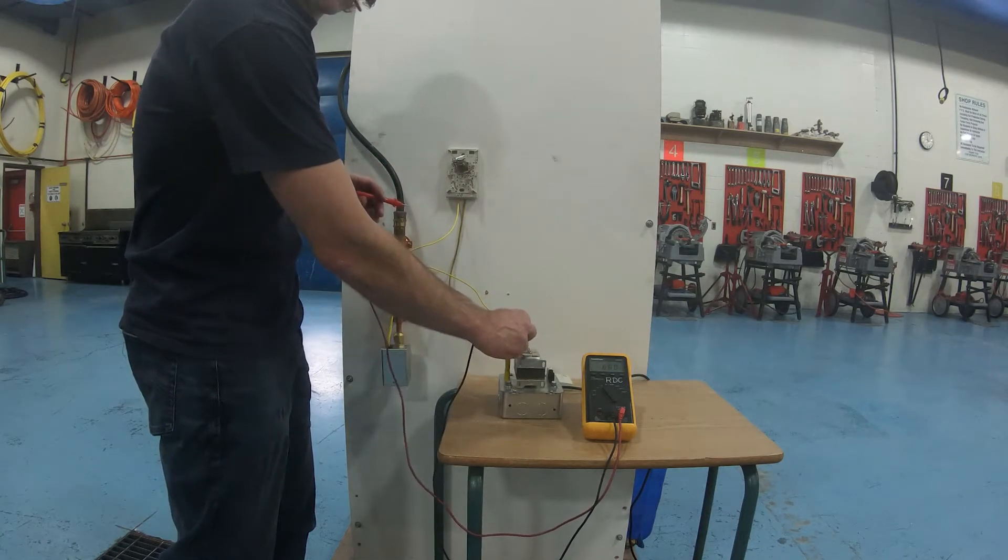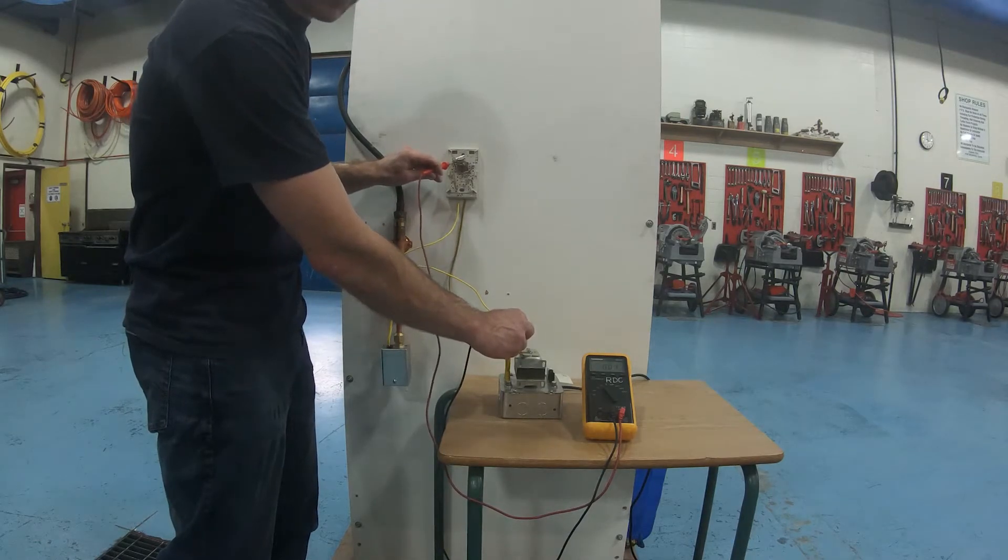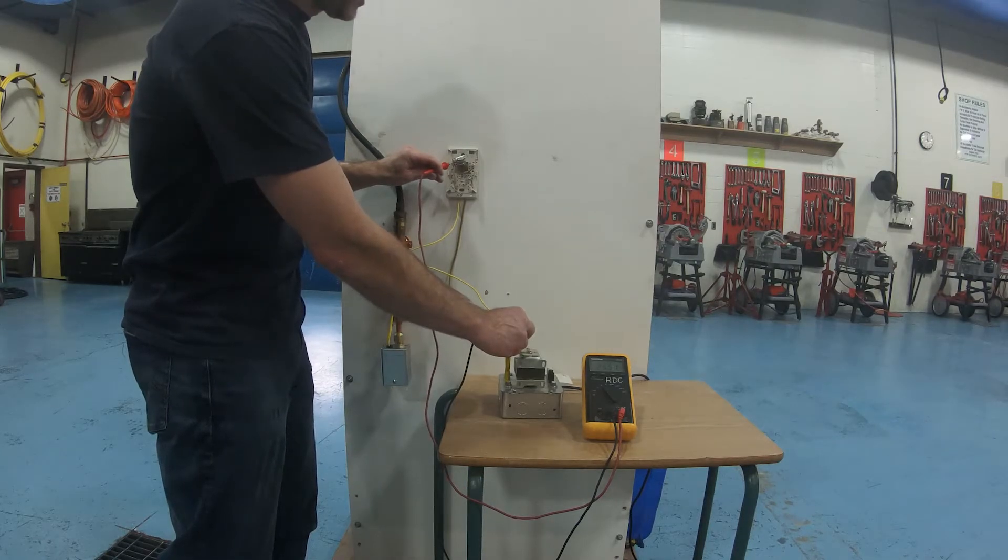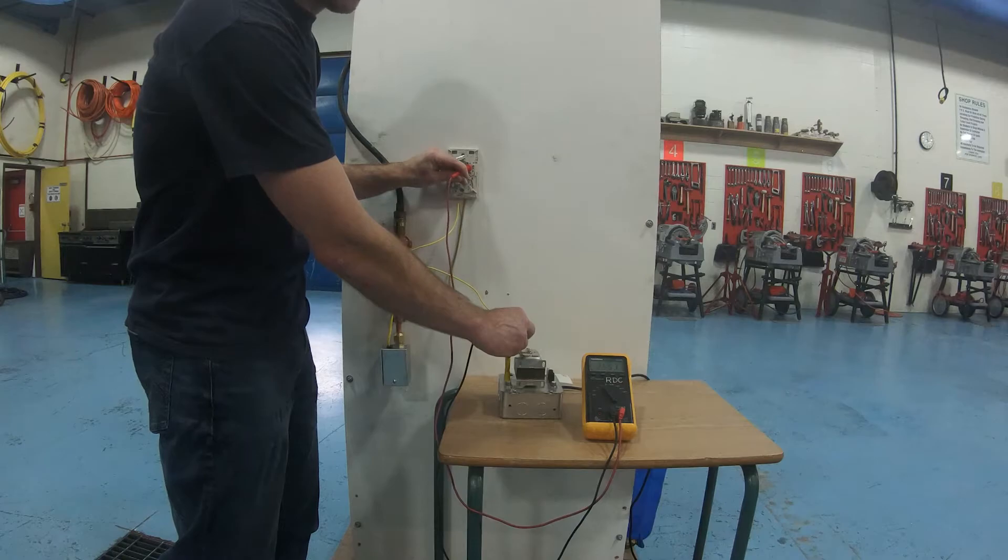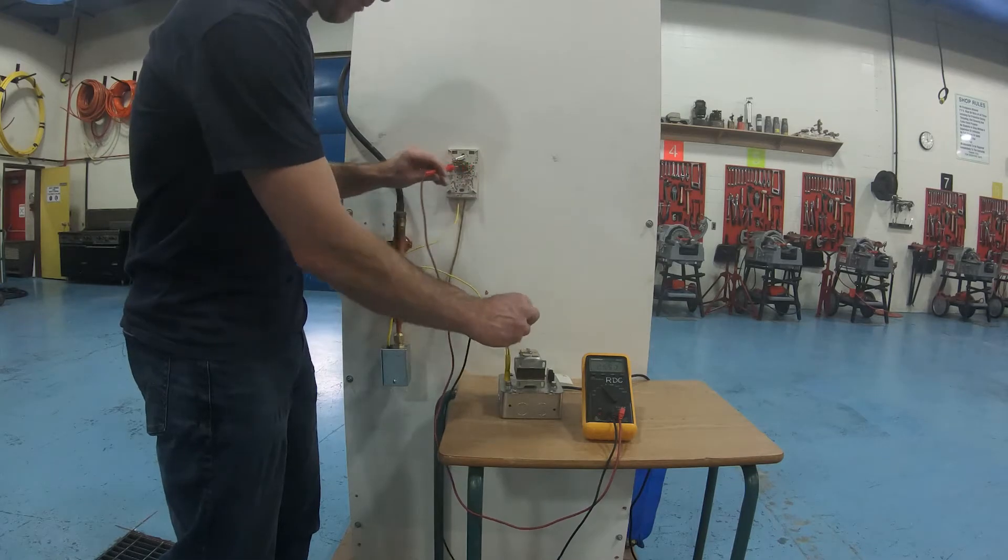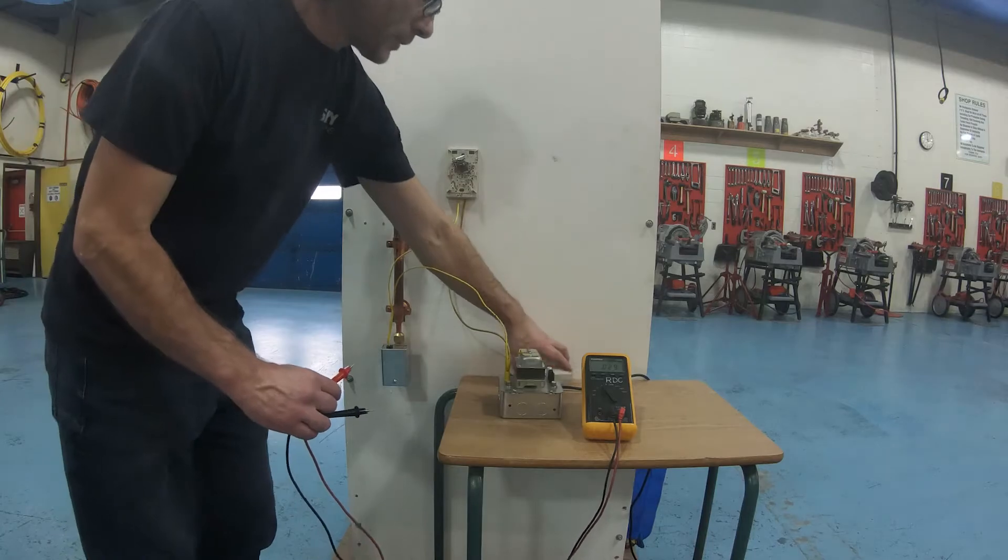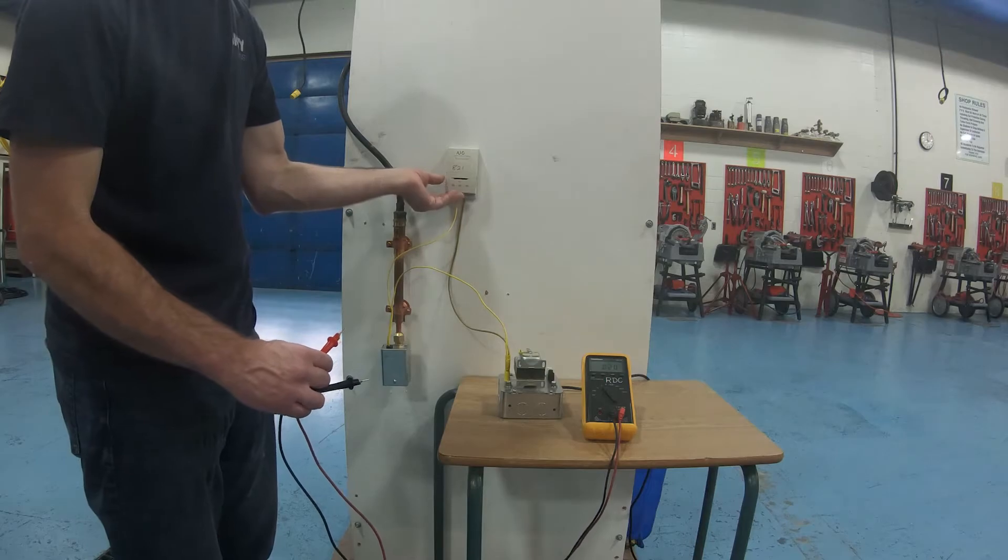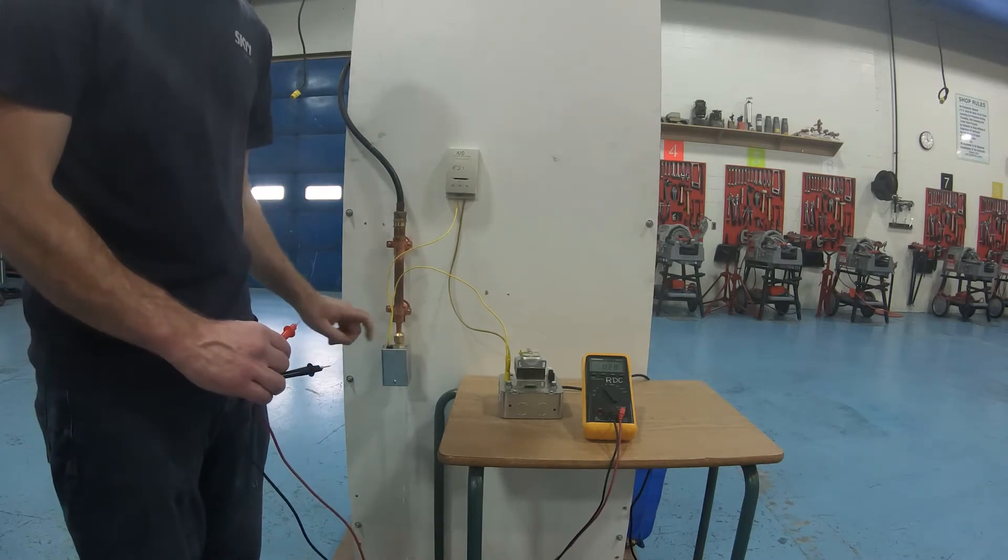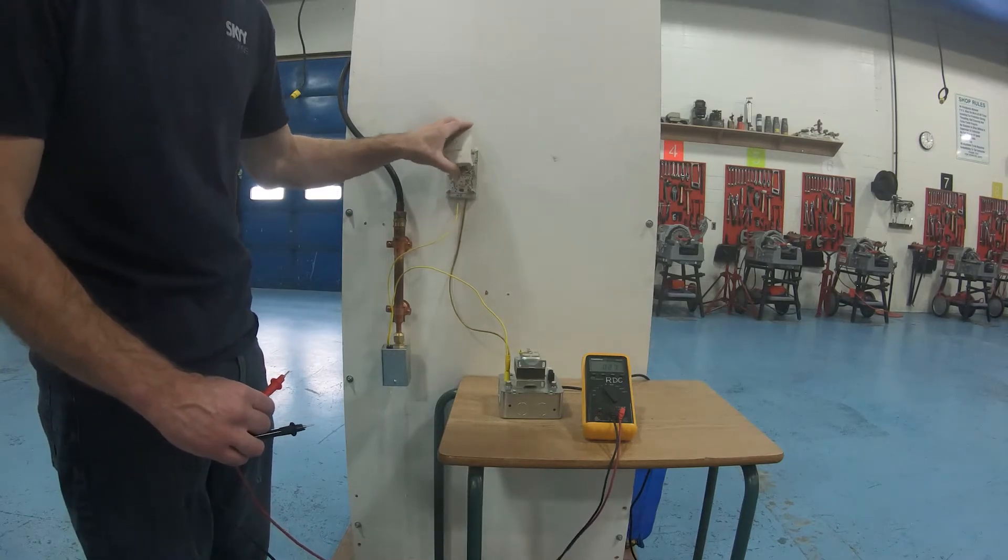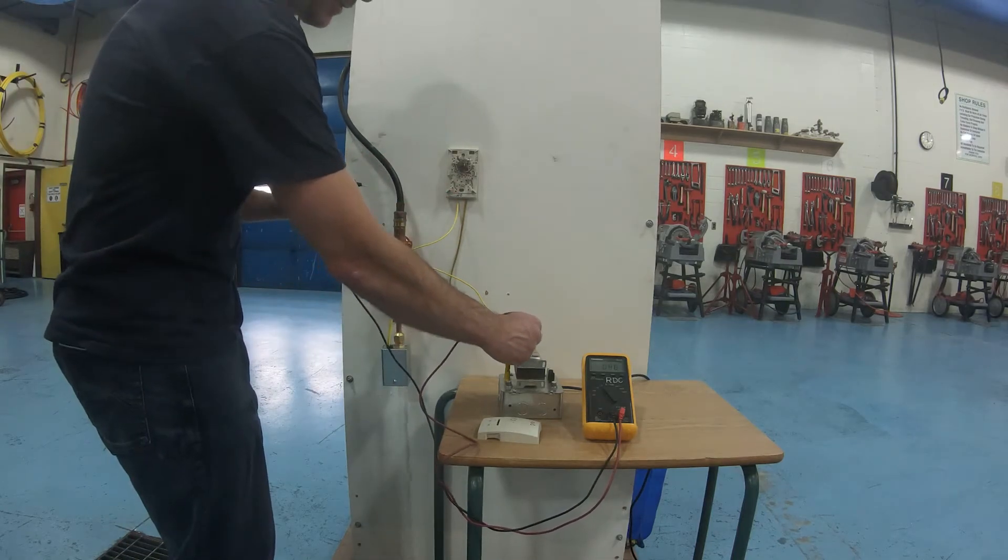On a regular thermostat, if I did this, so I'm just bringing one lead over to this side of the 24 volt transformer and I'm going to bring it to this side, this is the power side of the thermostat. Notice how I'm showing 25.5 volts. Now what I should be getting on this one, on a regular normally closed thermostat, is zero, but notice how I'm getting 25.5 volts. So power is flowing through the thermostat to the zone valve. What I'm going to do is turn the thermostat up.